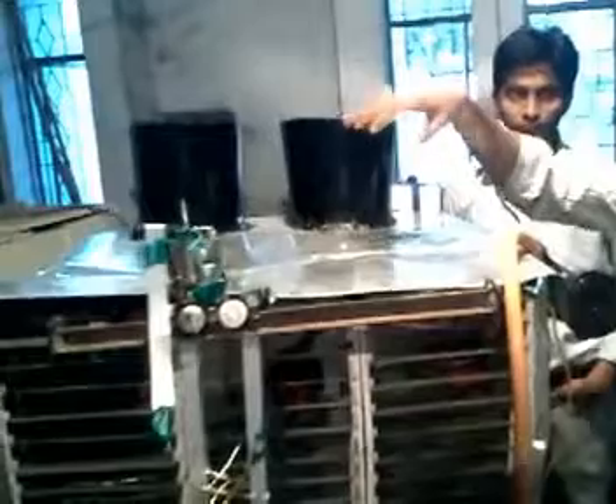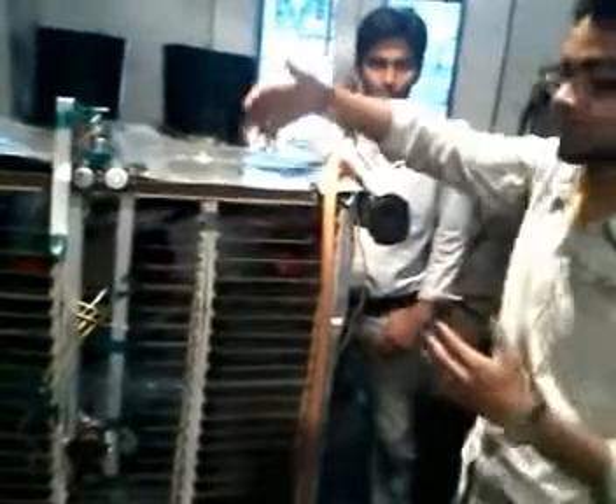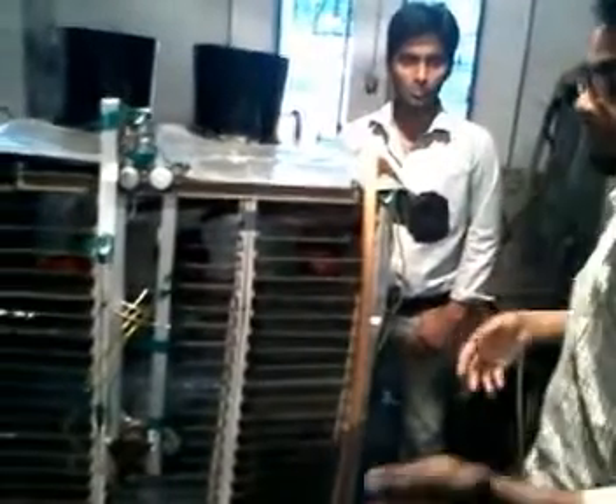So what is the purpose of using this forced fan? Suppose my induced fan is running and my plant is in running condition. In case this induced fan goes out of service or any problem occurs, I would need to shut down this tower, which would affect my condenser. Here, we need not do that. If the induced fan fails, my forced fan automatically starts. I'll go through this working experience this evening.